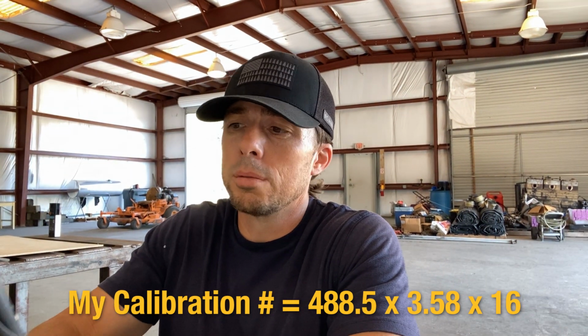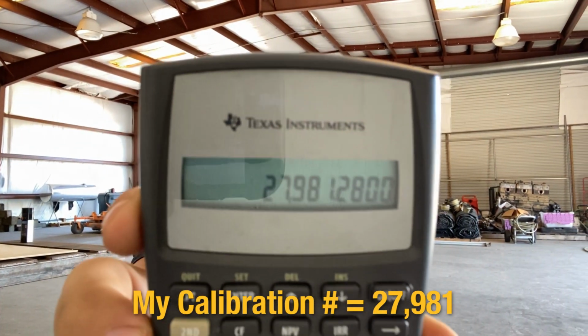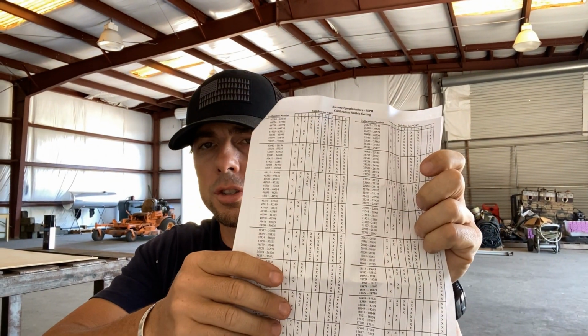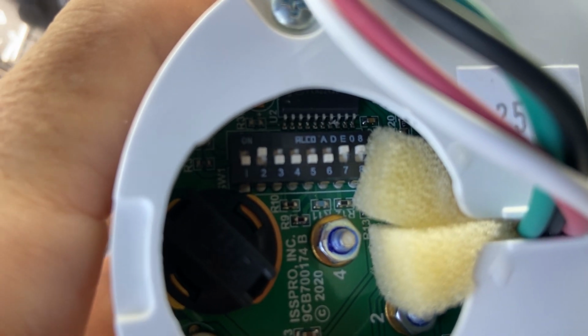So my number comes to 27,981. On the second page of the instructions, we look up the number 27,981 and find the dip switch settings. For this one, it says the dip switches that will be set to on are 2, 7, and 8. See, 2, 7, and 8 are on, the rest are off. Part of this is we've got to test it, see how far it's off, and then use a different calibration method to dial it in.